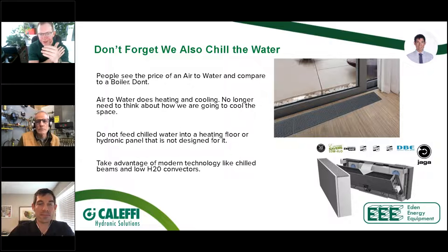Both of these units are designed to do radiant cooling. They have convectors built into them. They have drain pans built into them. So literally all you're doing is running a half inch piece of PEX to it. You're going to run it off a secondary manifold, and you're now air conditioning that space in a very simple, easy way to do it. And at that point, you've eliminated the discussion of why are you more money than a panel rad? I'm more money than a panel rad because I produce heat at a much lower water temperature. And by the way, I can also do the air conditioning.